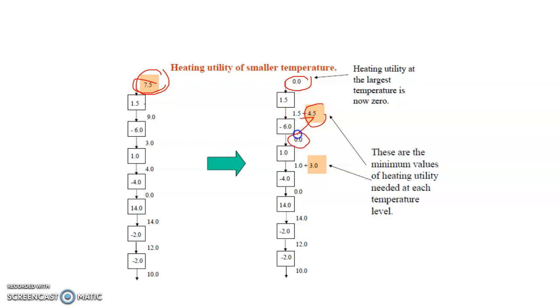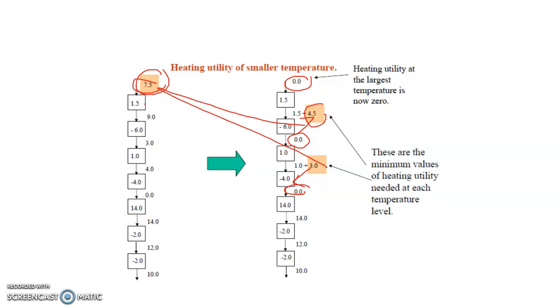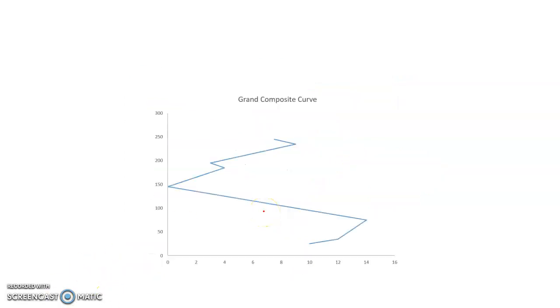Instead of supplying all the utility at one temperature, you don't supply any utility at the top interval but supply 4.5 megawatt at the next level — making the cascade value zero — and then add 3 more units at another interval, again making it zero. The total amount of energy required remains 7.5, but now it is supplied at two different temperature levels, which ensures the cost of the utility is naturally less compared to supplying all 7.5 at the highest temperature. These are the kinds of insights we get when we plot the GCC.